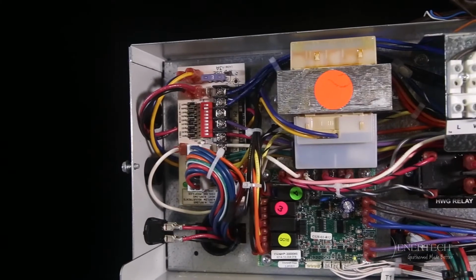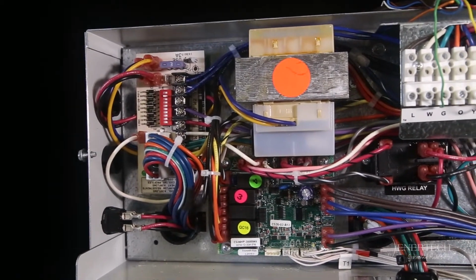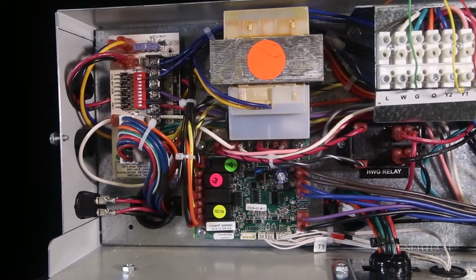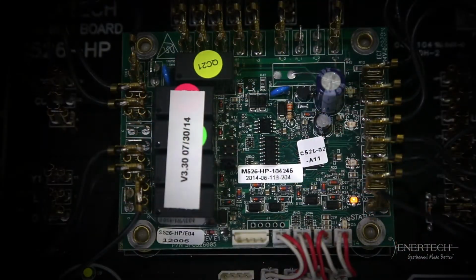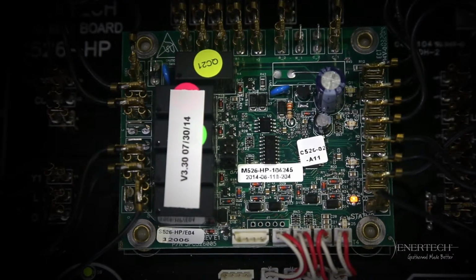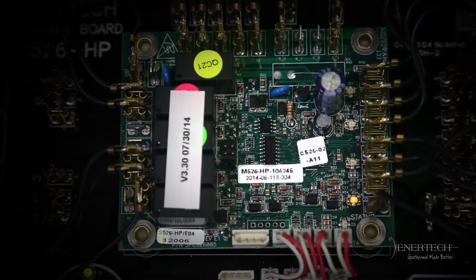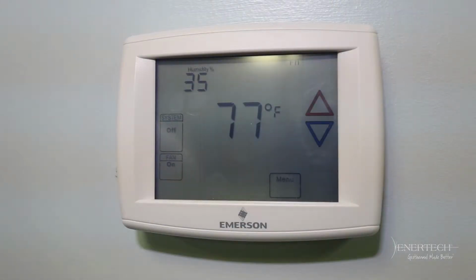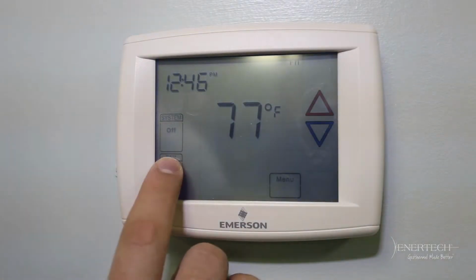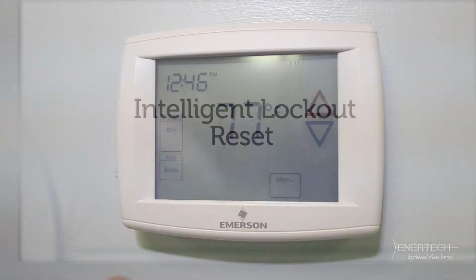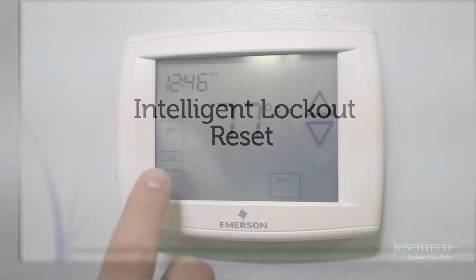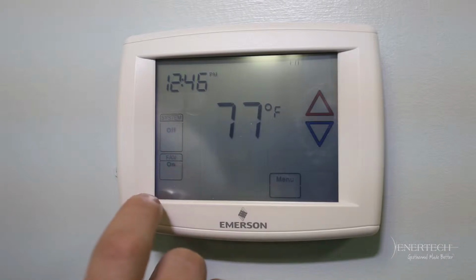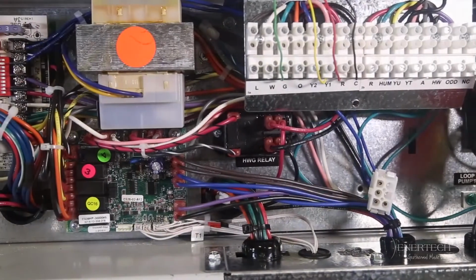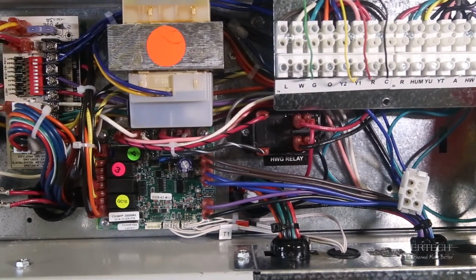The fault retry feature is designed to prevent nuisance service calls. All faults except over/under voltage are retried twice before finally locking the unit out. There is an anti-short cycle period of 5 minutes between fault retries. On the third fault within 30 minutes, the board will go into lockout mode and the call for service indicator on the thermostat will illuminate. If the thermostat is powered off for 1 minute, then back on, it performs a soft reset and the board will reset. The last fault will be stored in memory for ease of troubleshooting. If power is interrupted to the board, the fault memory will be cleared.